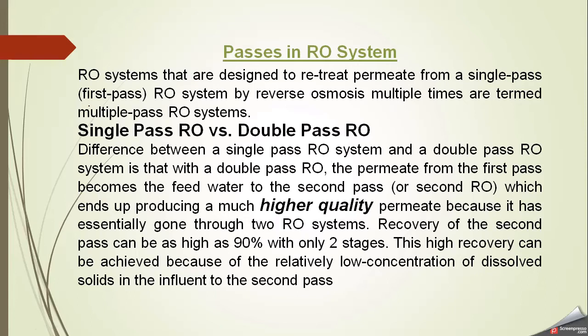The difference between a single pass and a double pass RO system is that the permeate from the first pass becomes the feed of the second pass. Due to feeding this higher-quality permeate into the second pass, we get much higher quality water at the final output. Recovery of the second pass can be as high as 90% with only two stages. This high recovery is achievable because of the relatively low concentration of dissolved solids in the influent to the second pass.